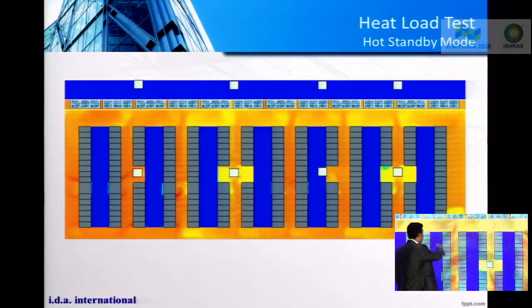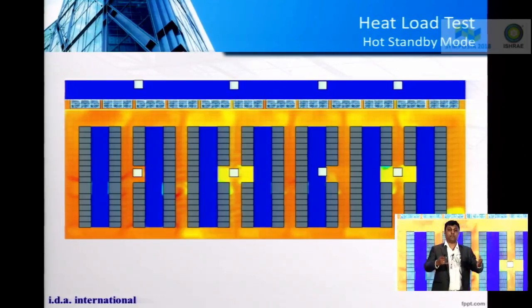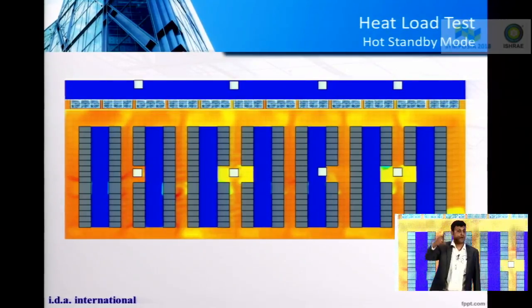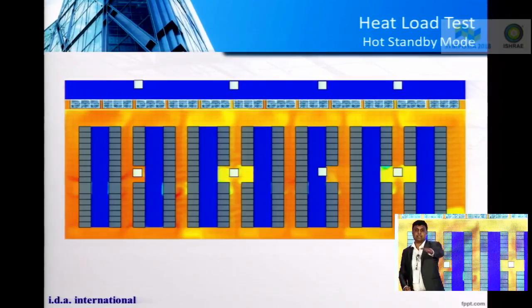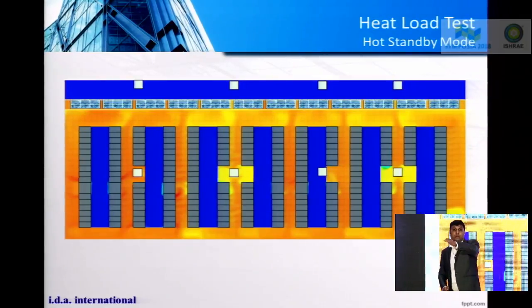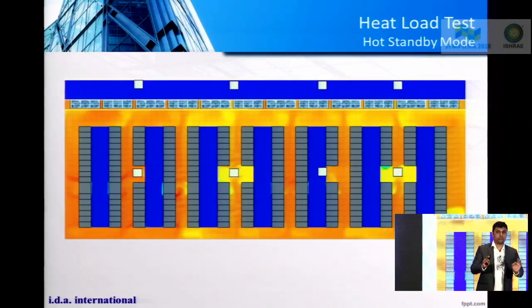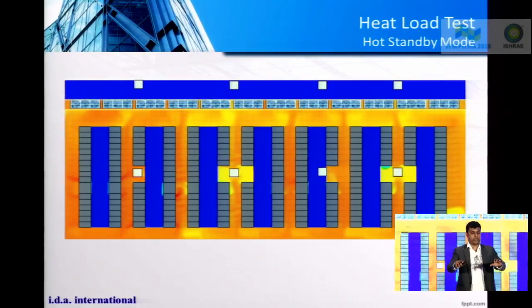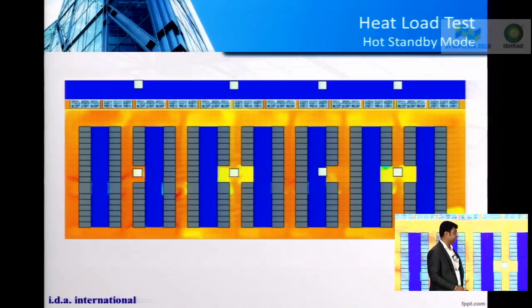So I can run all the CRAC units and start loading the data center from 25% to 50% to 75% to 100%. And throughout the number of hours that I'm loading the data center, I have to keep a close watch on the temperature and the relative humidity in the cold aisles and the hot aisles.